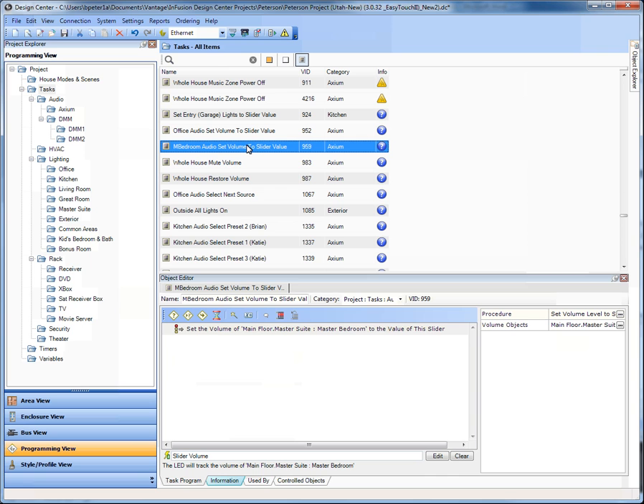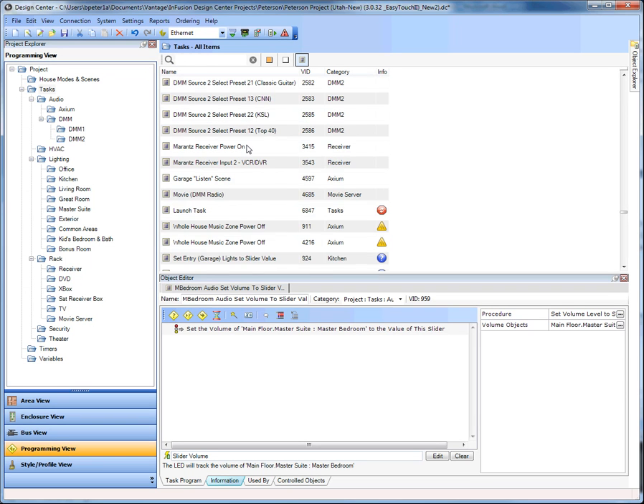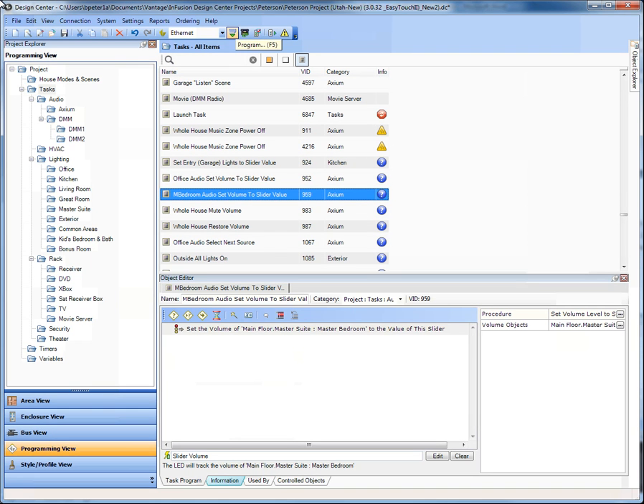I'm going to scroll down and find these. If I had a bunch of unused tasks, I can hold down Shift and click, then delete them or address them one at a time and see all my error messages inside the task editor. You'll see catastrophic failures in red, higher-profile warnings in yellow like blocking procedures or missing elements, and blue for more of a heads-up — like this task isn't used but it's not going to cause any system problems.